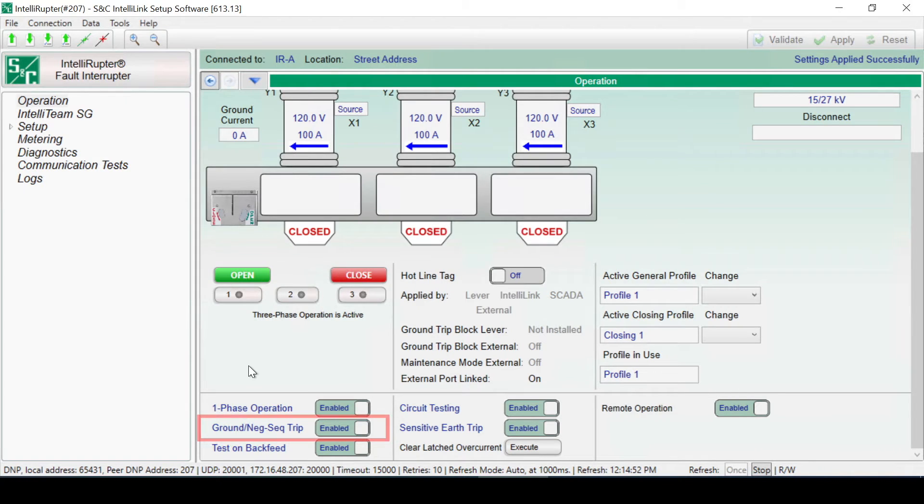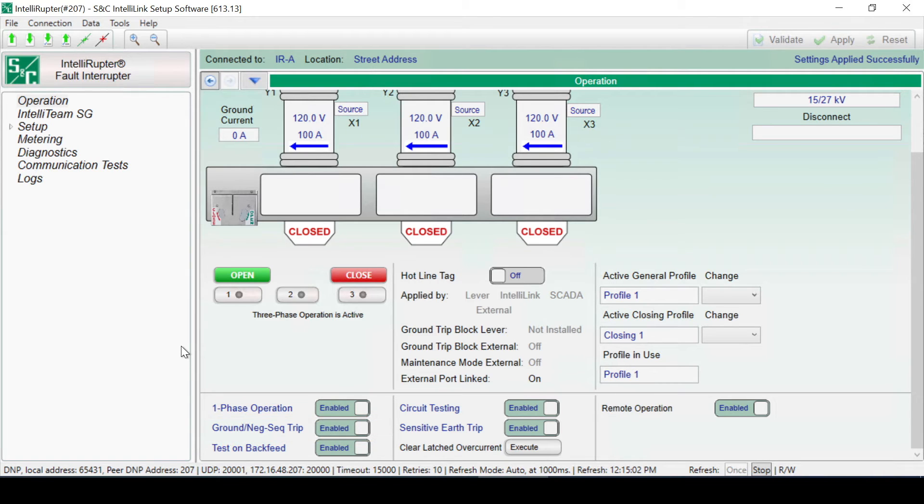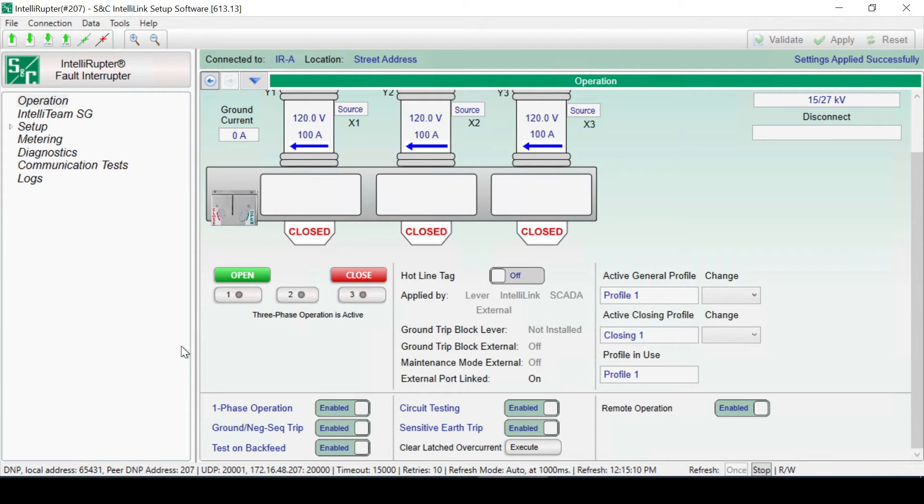The Ground Trip block can be enabled or disabled through IntelliLink software by clicking on the Ground Trip slide control. However, if Ground Trip block is physically applied on the fault interrupter, it cannot be disabled through IntelliLink software. If the switch is being configured using a docking station, the Ground Trip block will be on and not available to change via IntelliLink software.